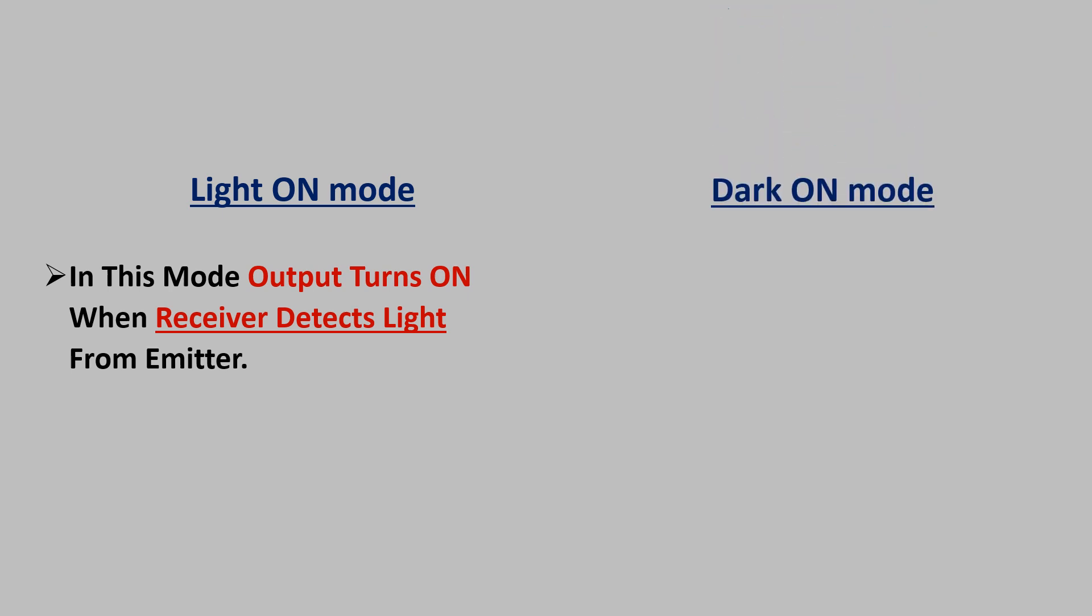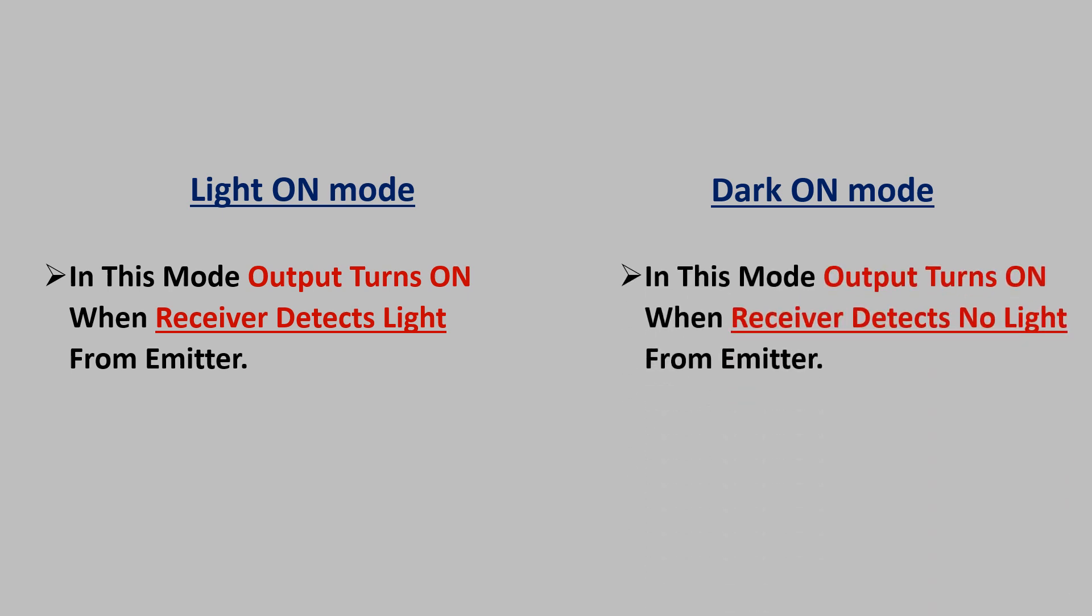Light on refers to the state that the receiver of the photoelectric sensor receives sufficient light. In this mode, the output turns on or load is energized when the receiver detects the light from the emitter. Dark on means there is no light reflected to the receiver of the photoelectric sensor. In this mode, the output turns on or load is energized when the receiver receives no light.